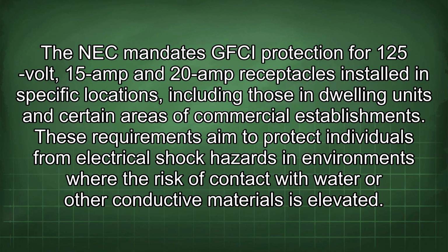The NEC mandates GFCI protection for 125-volt, 15-amp and 20-amp receptacles installed in specific locations, including those in dwelling units and in certain areas of commercial establishments. These requirements aim to protect individuals from electrical shock hazards in environments where the risk of contact with water or other conductive materials is elevated.